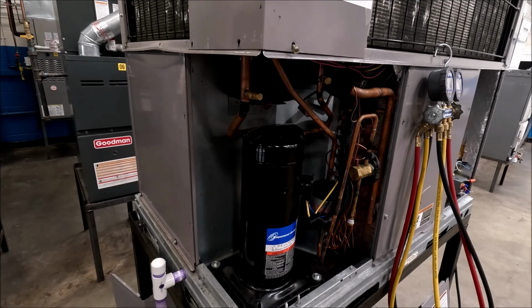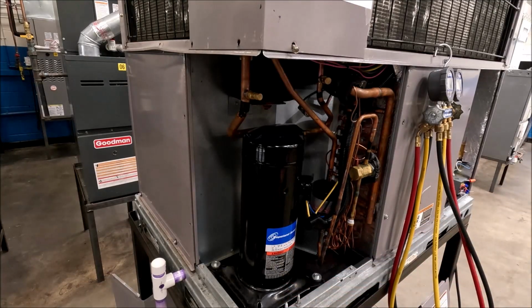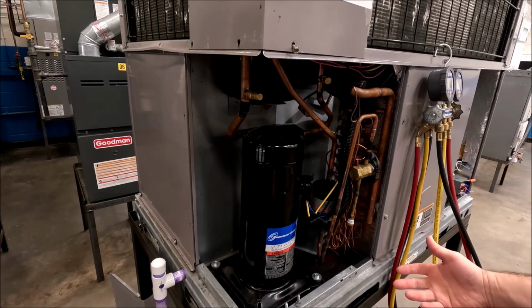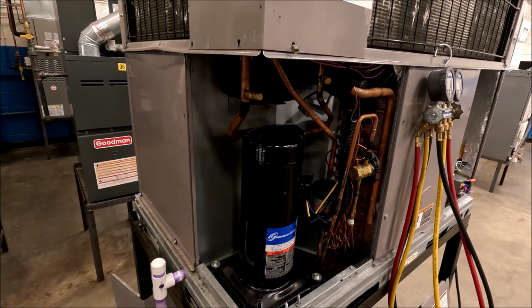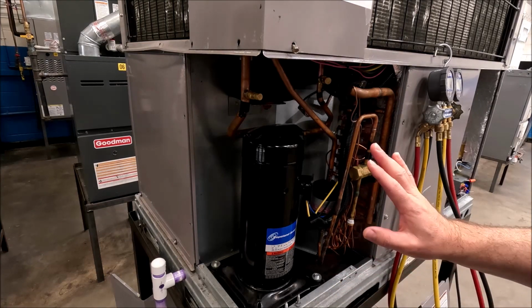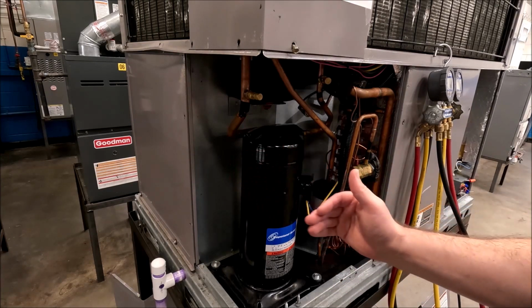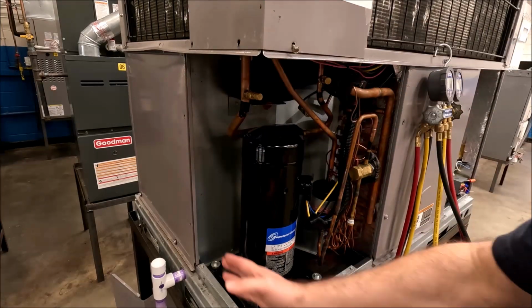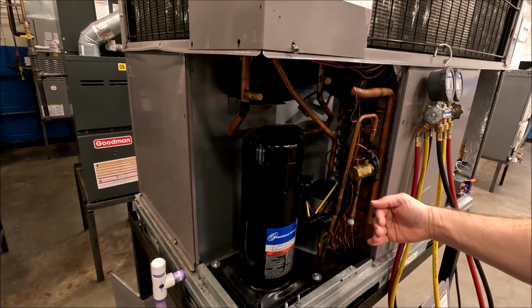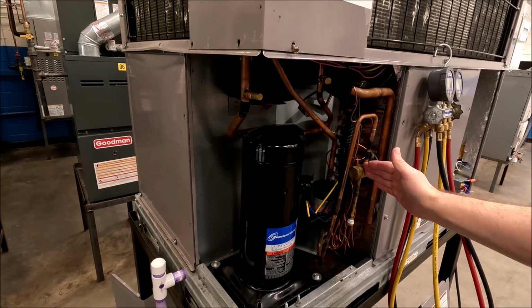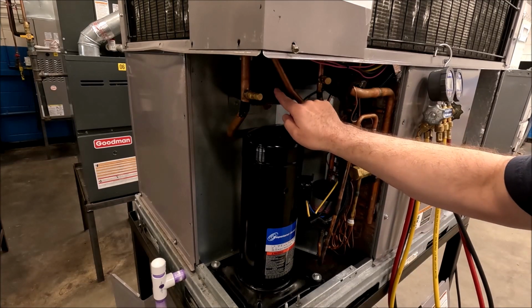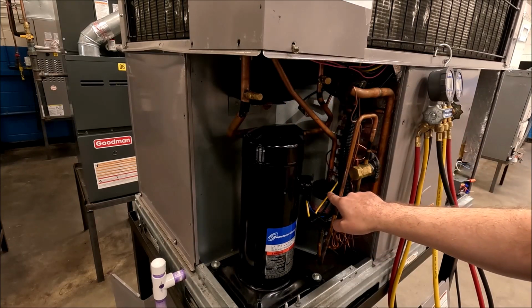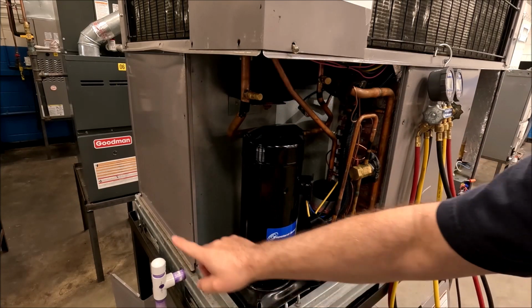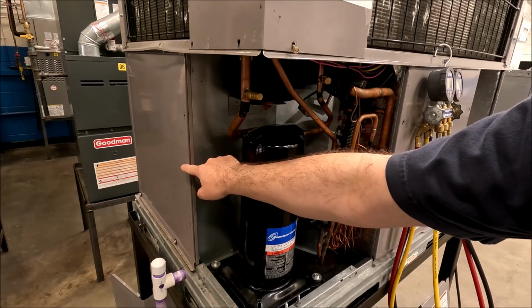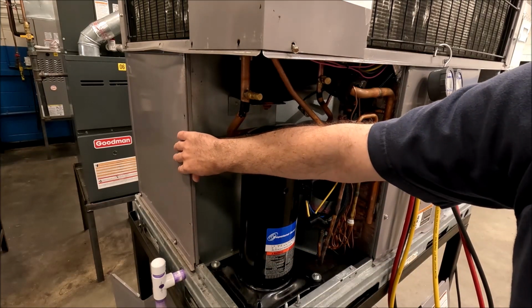All right, so here we are on a single stage heat pump unit, and this is of course a package unit. It's one of the ones I've done videos on in the shop before, I believe. If not, this is going to be the first time. But what I've got here is I've just rolled it into a position in the shop and took the corner cover off. And this is typical of a lot of units. Right here on this side corner is your compressor area and your indoor metering device. If you look above it, I've got a refrigerant accumulator, and I've also got the filter dryer in the liquid line back here. Right, this panel to the left is an access point to the evaporator coil.